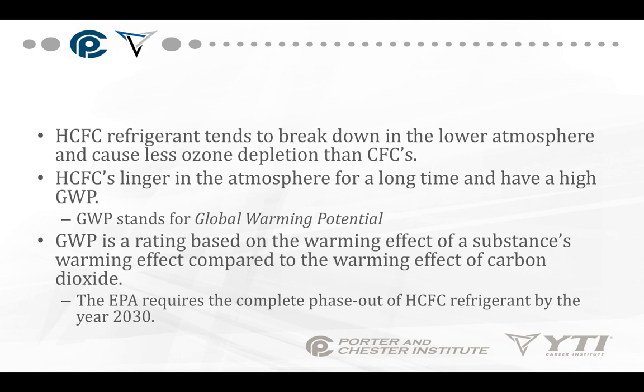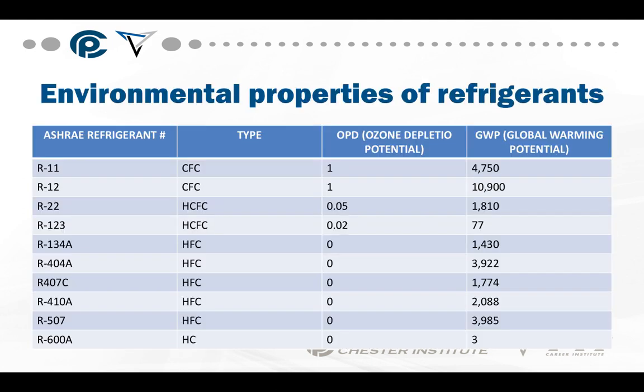HCFC refrigerants tend to break down in the lower atmosphere and cause less ozone depletion than CFCs do. However, the tradeoff is that HCFCs linger in the atmosphere and have a higher GWP — global warming potential. The GWP ratio is based on the warming effects of a substance compared with the warming effect of carbon dioxide. The EPA requires a complete phase-out of HCFC refrigerants by the year 2030 because of the global warming potential. On the reference chart, note that R12 has an ODP of 1 and HFCs have an ODP of 0.